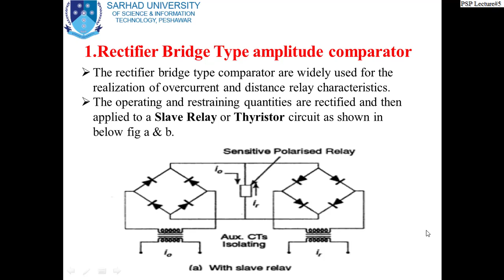Now, this is another arrangement. This arrangement is the same type of rectifier arrangement. We have two rectifiers, bridge rectifier rather. One is of course rectifying the operating current, and one is rectifying, of course, the restraining current. But instead of feeding the output of these currents to a slave relay, they are given to a thyristor circuit through a transistor arrangement.